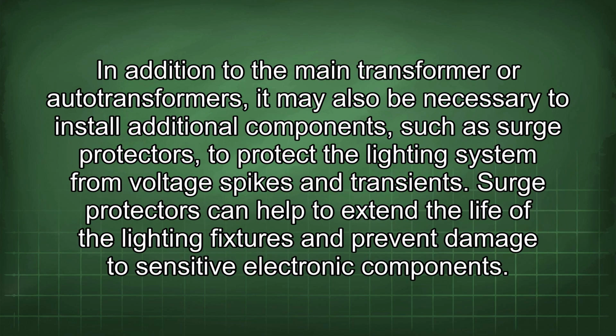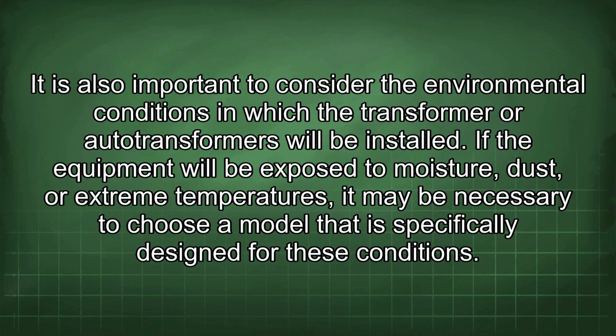In addition to the main transformer or autotransformers, it may also be necessary to install additional components, such as surge protectors, to protect the lighting system from voltage spikes and transients. Surge protectors can help to extend the life of the lighting fixtures and prevent damage to sensitive electronic components. It is also important to consider the environmental conditions in which the transformer or autotransformers will be installed.